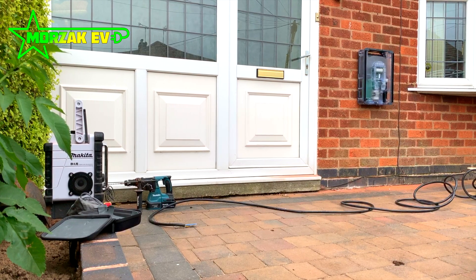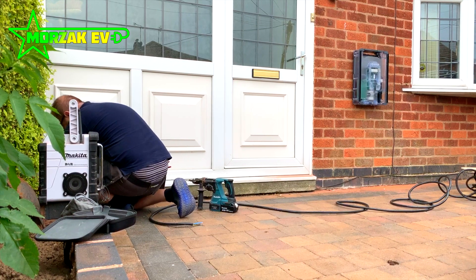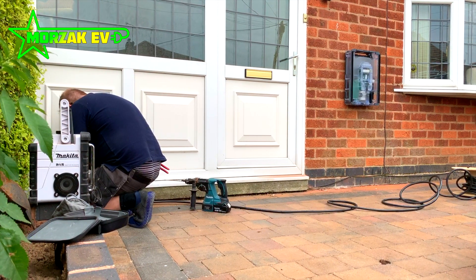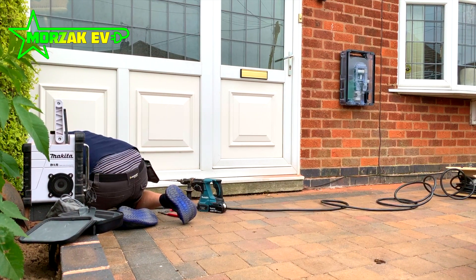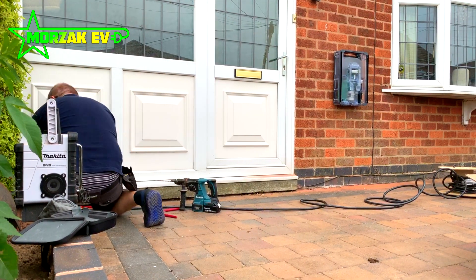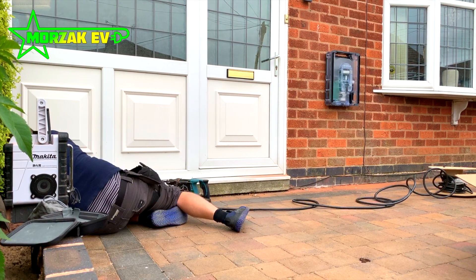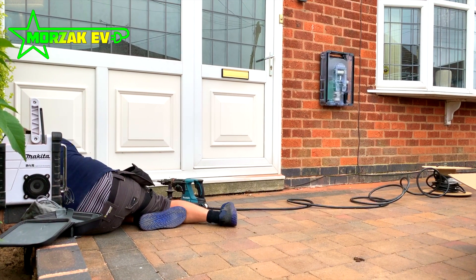If your general house usage isn't high — say you have a gas cooker and no electric shower — then it's probably not a worry. But if you do have these items, we can do a calculation to work out how much your usage is, and with the charge point included, this might all need upgrading. Most DNOs do not want a charge point on a looped supply, so getting the house fuse upgraded gives you future proofing. We are covering load management in a separate video — I'll leave a link in the description below once that's done.